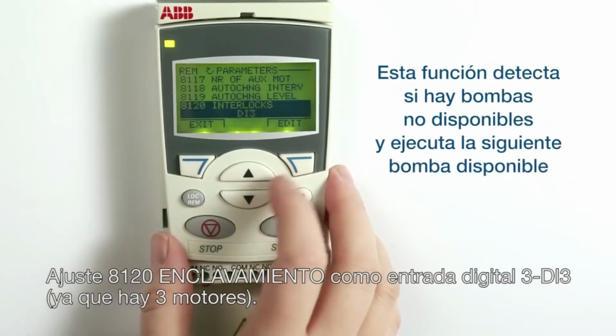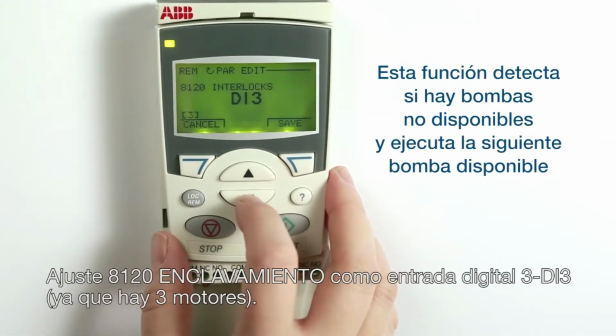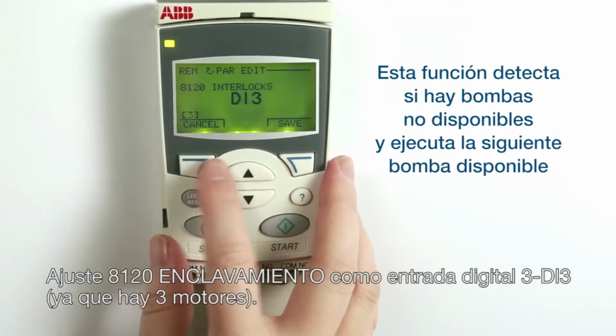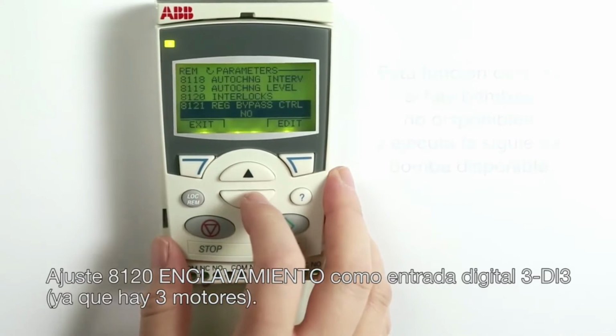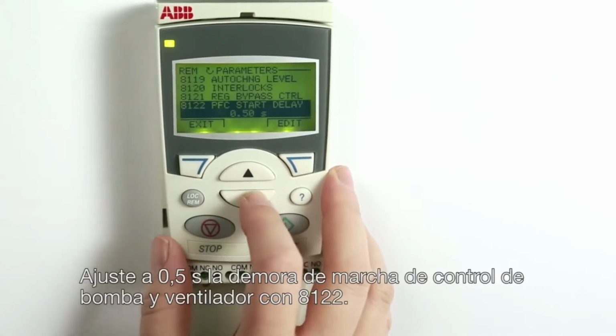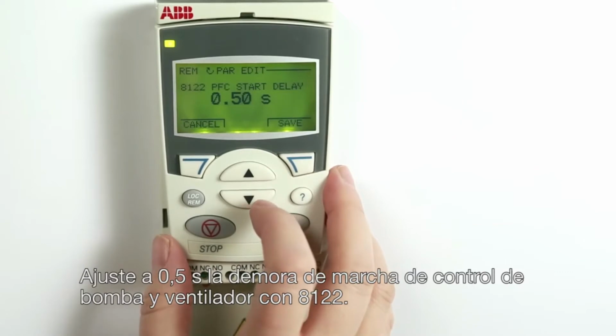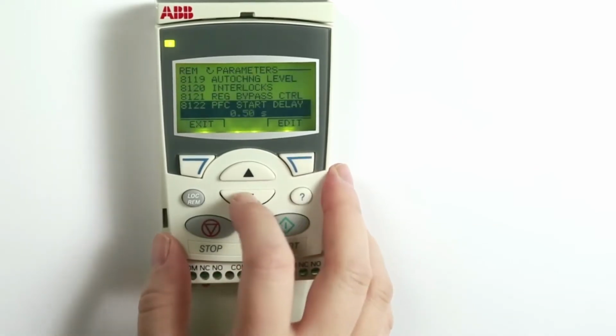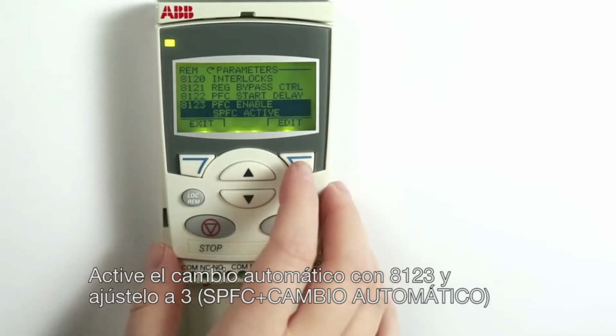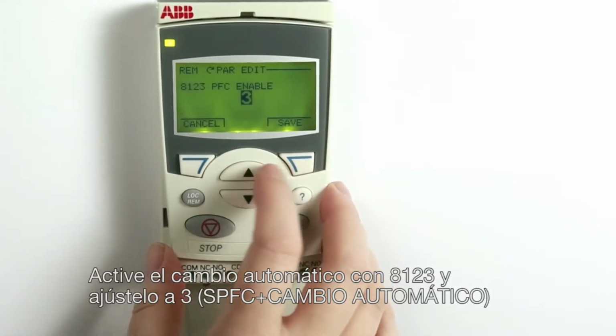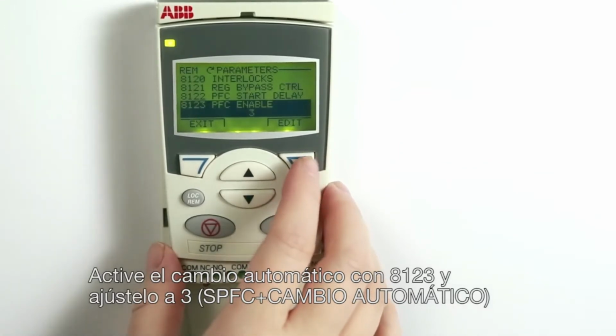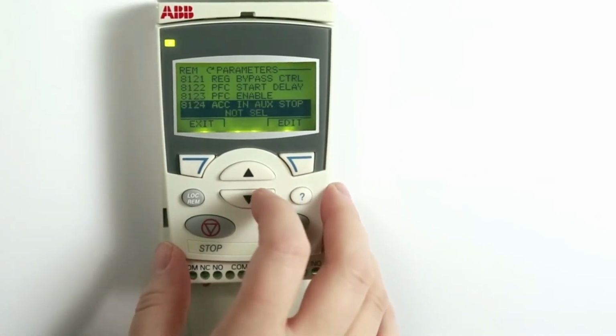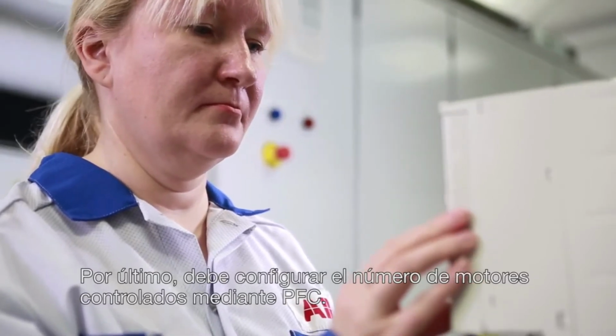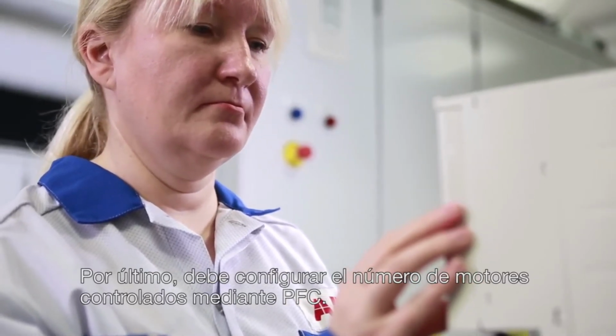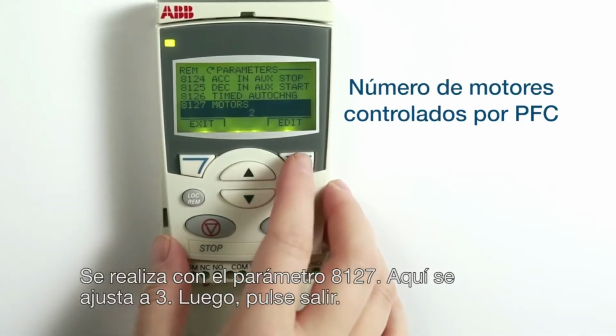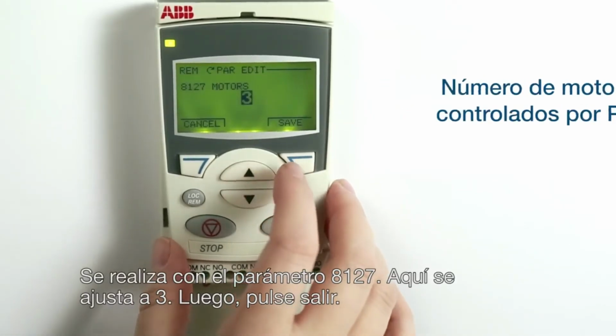Then we set parameter 8120, interlocks, to take the input from digital input 3, DI3, since we have 3 motors. Next, we set the start delay for pump and fan control with parameter 8122. We leave it at 0.5 seconds. Now we enable the auto change functionality with parameter 8123 by setting it to 3, meaning SPFC plus auto change. The last parameter to be set in this PFC group is the number of PFC controlled motors. This is done by parameter 8127. It is set to value 3 in this example.